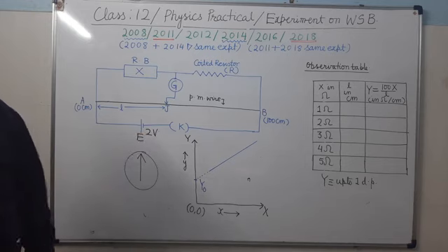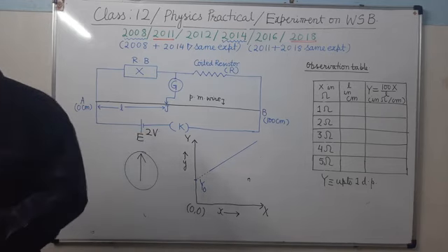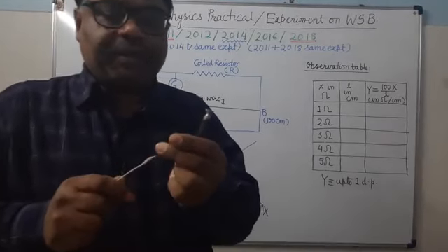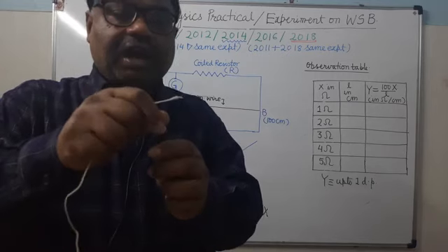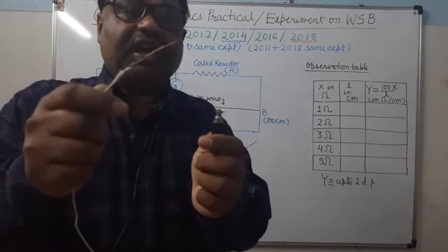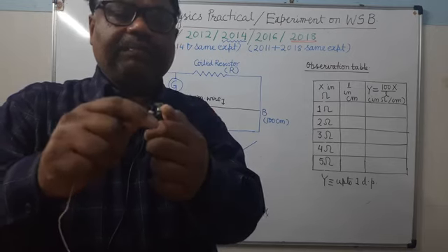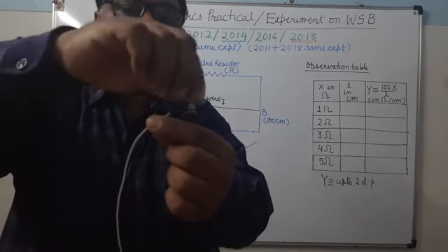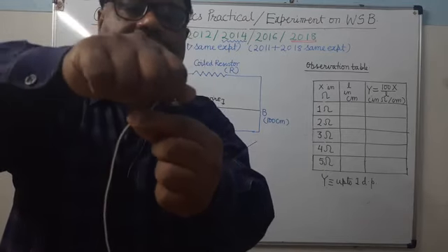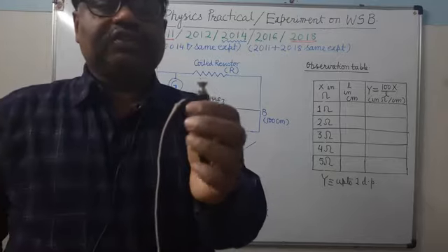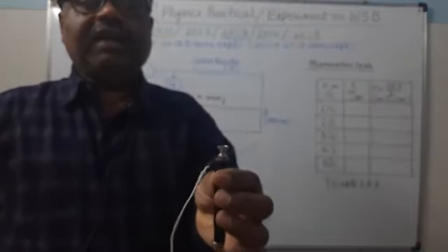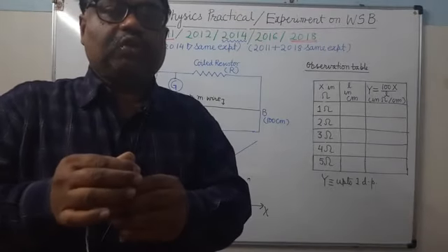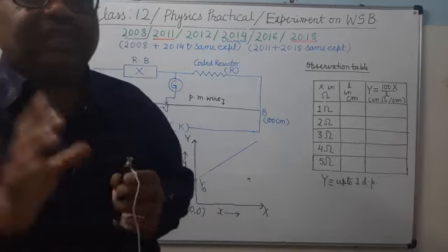This way you will connect. And how will you connect the wire? Already I have explained, always connect the wire in the binding terminal in such a way that only half turn is made. You only bend half a turn. You can see here, because when you connect in half turn, the connection becomes very tight. There should not be any air gap. Otherwise what will happen? Extra resistance will be introduced. There should be no loose connection anywhere.